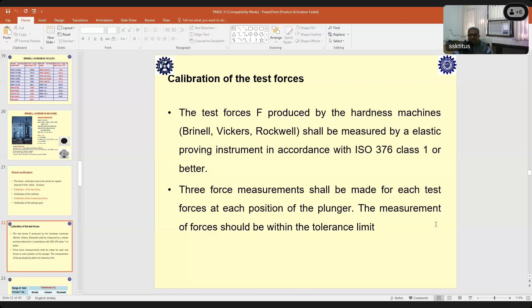Three force measurements shall be made at each test force at each position of the plunger. So this I have already mentioned. You have to rotate it, and you have to take at three different heights because of the thickness of the sample. Sometimes it varies. So all these factors you have to take into account when you are calibrating the hardness machine for the force component.